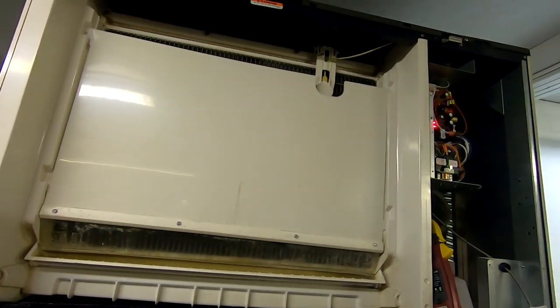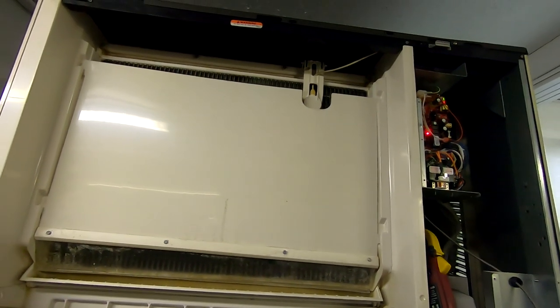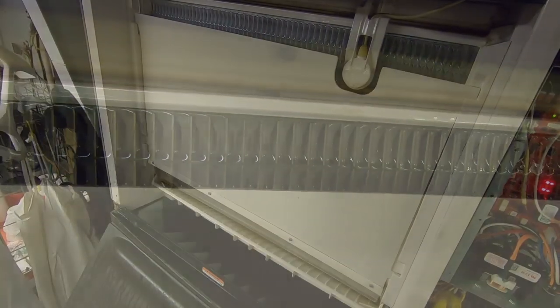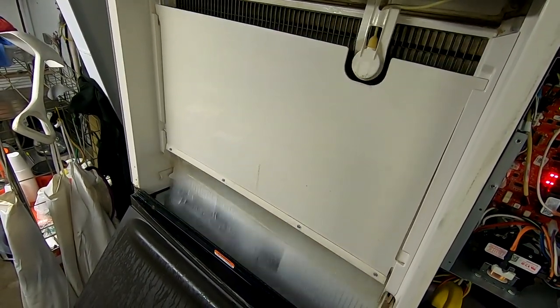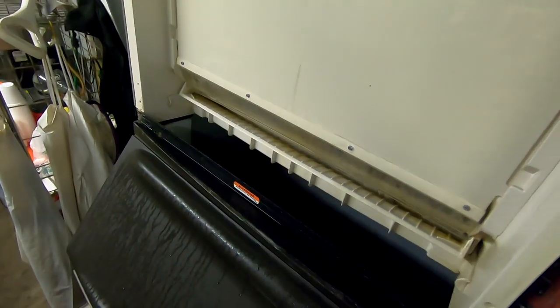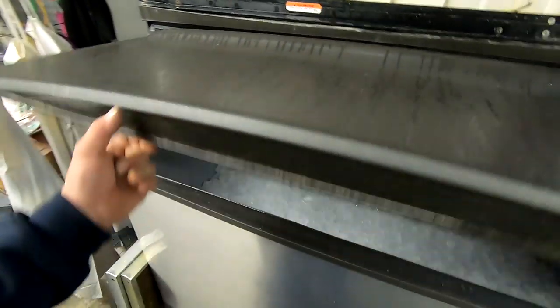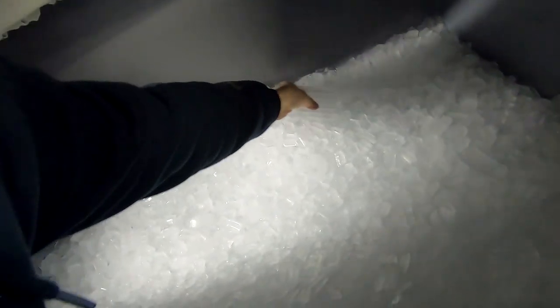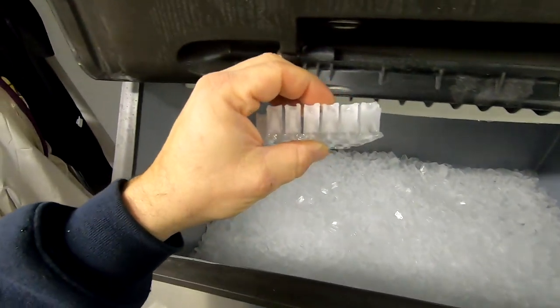One thing to keep in mind when an ice machine is low on refrigerant, you're going to have problems harvesting. You would think that you'd have problems freezing, but quite the opposite. Your problem is harvest. Takes more hot gas to get that plate hot and melt that ice off so it falls than it does to freeze it.